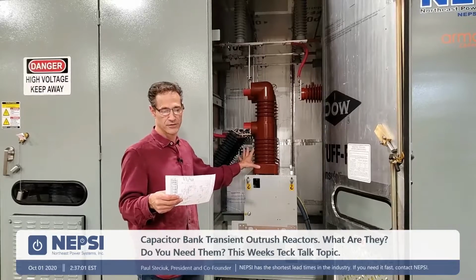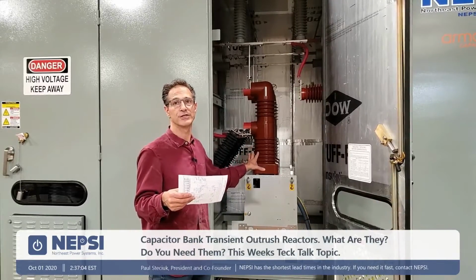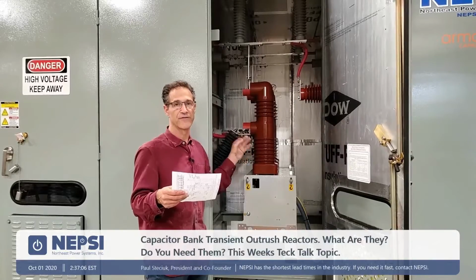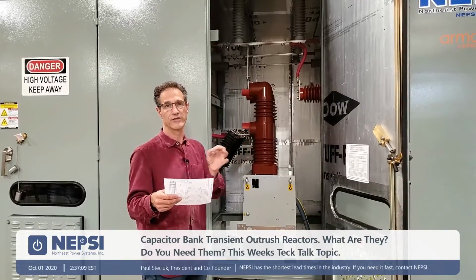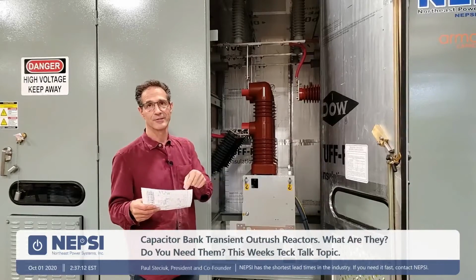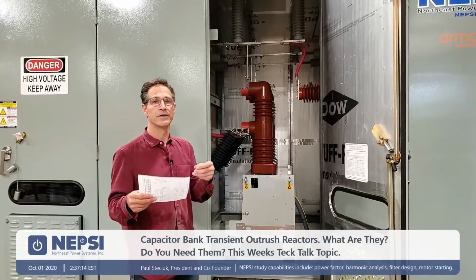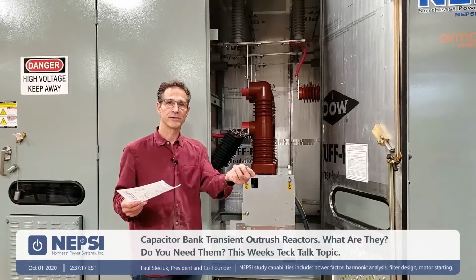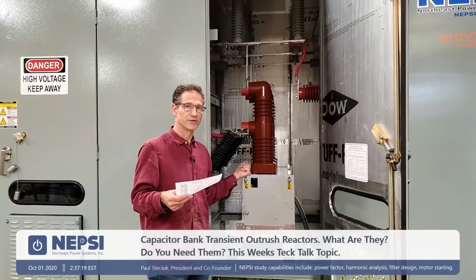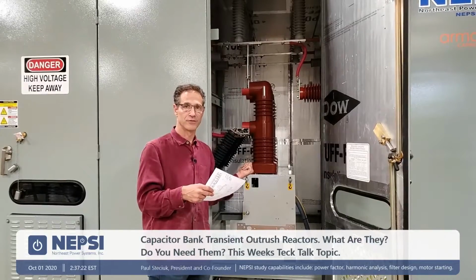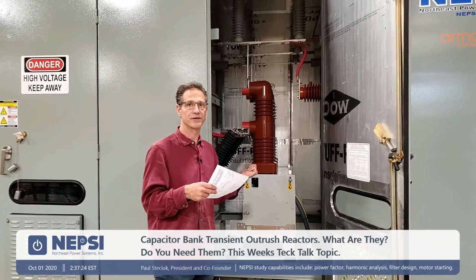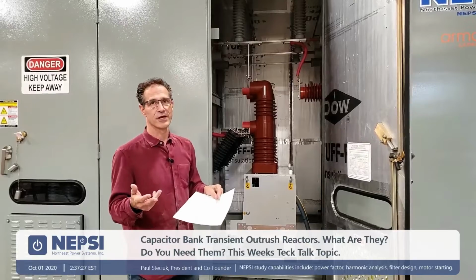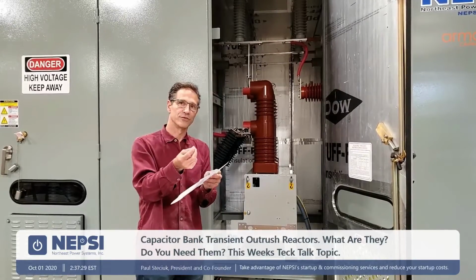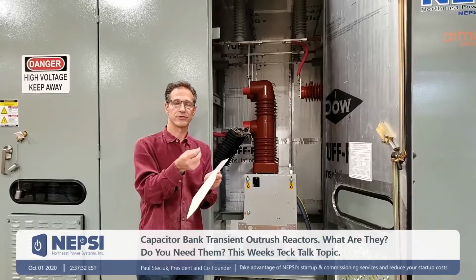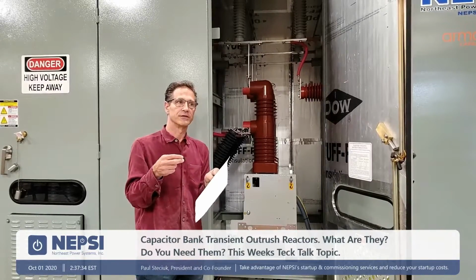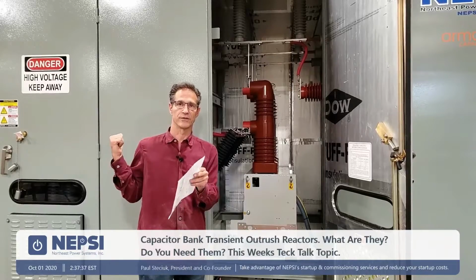It has a 10,000 operation count to it for a warranty and a 5-year warranty. So 5 years or 10,000 operations. It's stock at NEPSI, and that's key, stock at NEPSI. So if you have an issue with delivery time, you can come to us, and we're going to be able to ship you a cap bank within a very short period of time, because we're stocking these at NEPSI. It's something we can't do with the Southern States cap switcher, unfortunately, because of the resistor size. The resistor size, which is the pre-insertion resistor, really is sized based upon the MVAR rating of the capacitor.